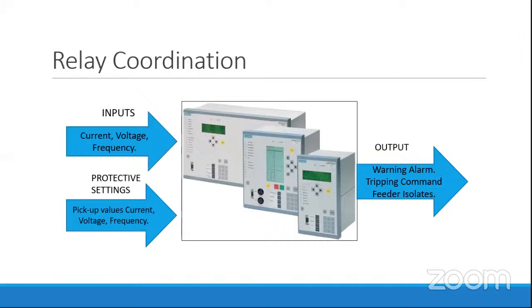So here in this figure, you can see a flow block diagram showing that this protective relay is simply a device which detects the current, voltage, and frequency. It will also detect the temperature for thermal overload of a transformer. We can say that for transformer protection, we have such protections. So these numerical relays have features which can sense the current, voltage, and frequency. With this measurement of current, voltage, and frequency, the relay will show the measurements of these quantities.